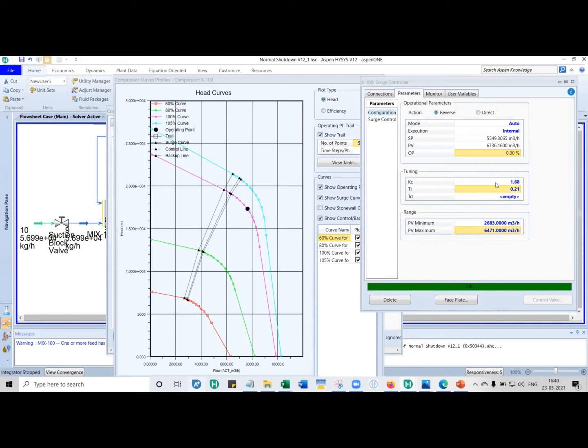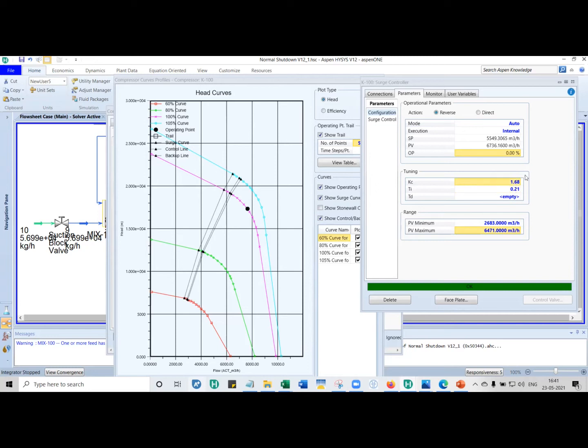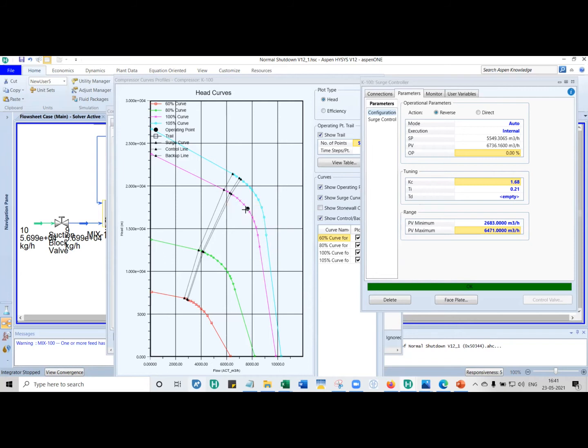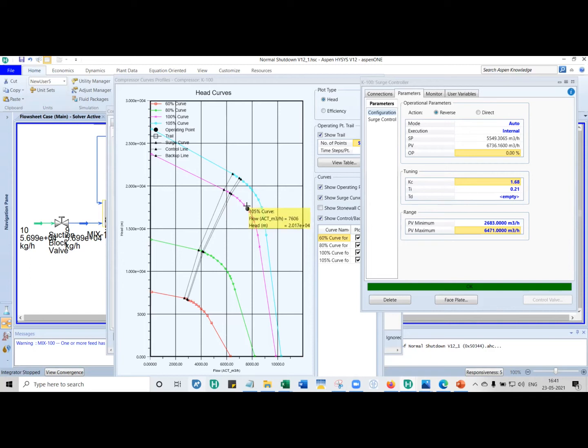Regarding the tuning, you can take the values for a flow controller, I think 2 and 0.1 or something. What I used to do was I put 2 and 0.1, and after I finished the model, then I do a stability test and keep changing the KC. I know only the trial and error method. I know of no other method. You can fix the TI and go on increasing the KC till you see some oscillations. That's the way I do it.